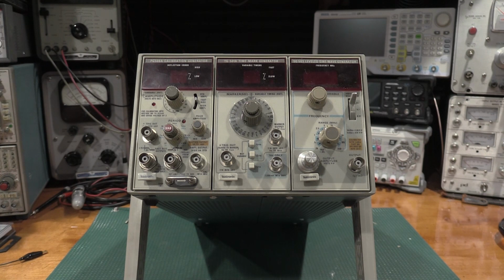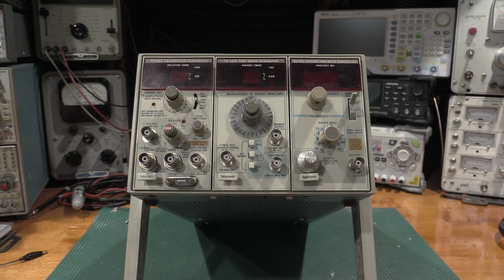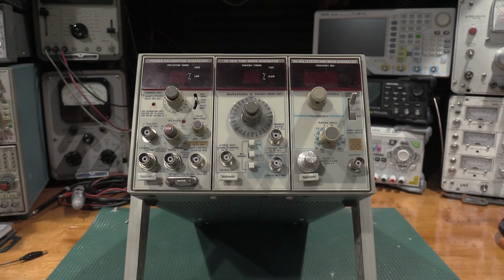That is not true for the SG504, which goes up to a gig, 1040 megahertz. The leveling head that's in that unit, you must use - if you don't have the leveling head, it won't work. The SG503 will work without it, the SG504 won't. That's a little bit of a difference between the two. The SG504s are starting to get very rare and very hard to find, and the leveling heads are getting even harder to find. So if you don't need it, stick with a 503 - it will be less expensive.